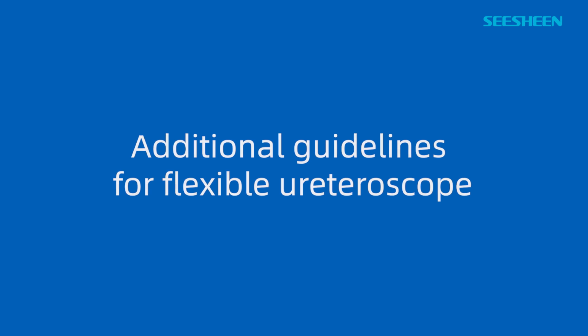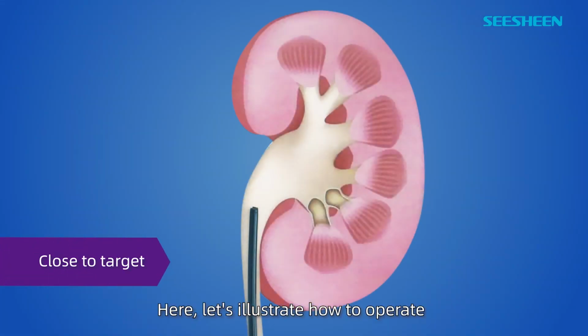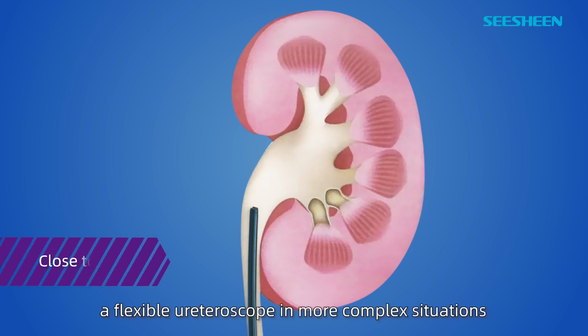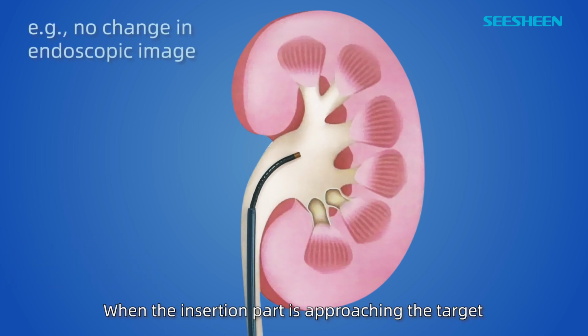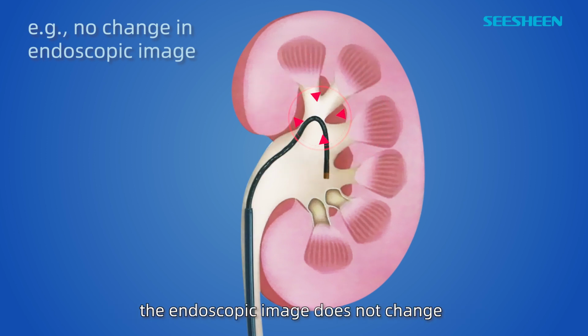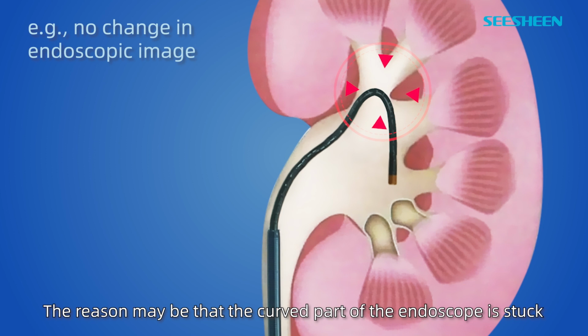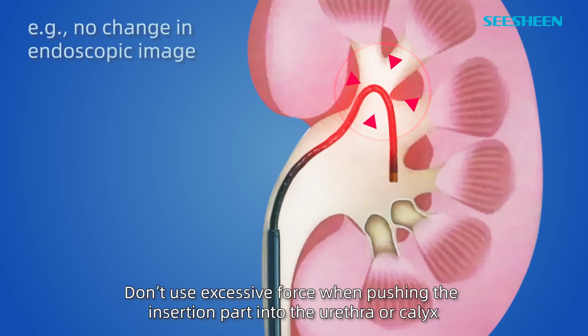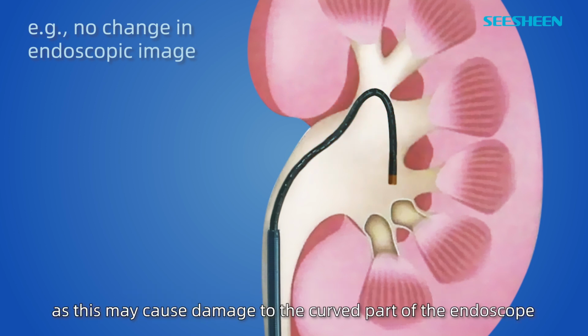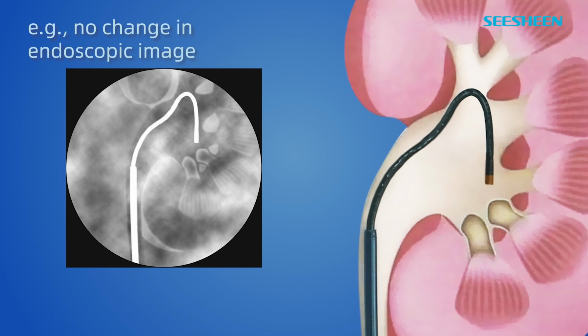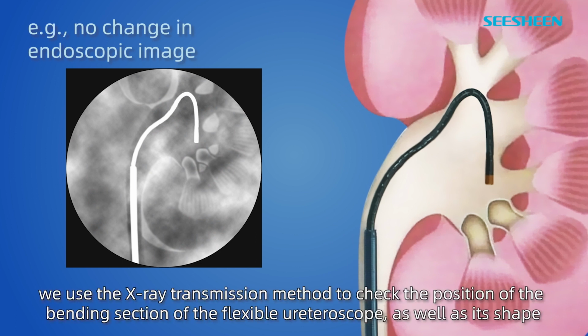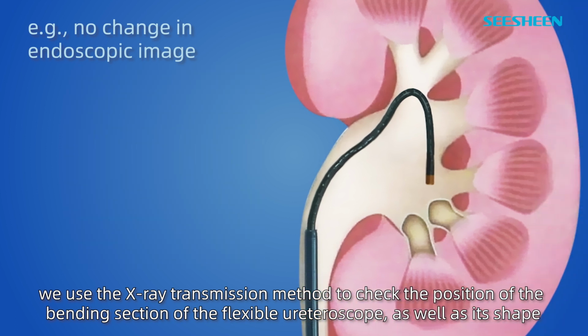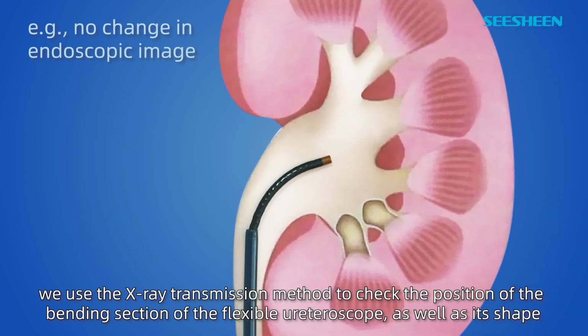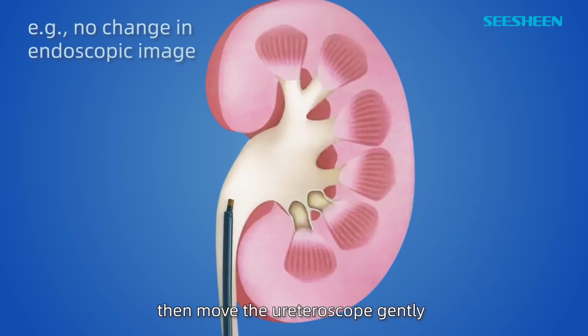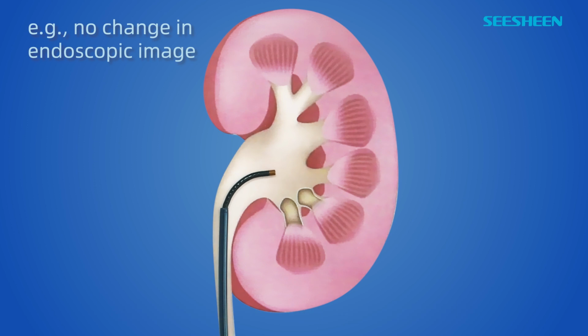Additional guidelines for flexible ureteroscope. Here, let's illustrate how to operate a flexible ureteroscope in more complex situations. When the insertion part is approaching the target, the endoscopic image does not change even if the insertion part is pushed. The reason may be that the curved part of the endoscope is stuck. Don't use excessive force when pushing the insertion part into the ureter or calyx, as this may cause damage to the curved part of the endoscope. In this case, we use the X-ray transmission method to check the position of the bending section of the flexible ureteroscope, as well as its shape, then move the ureteroscope gently and reinsert it when it can be moved smoothly.